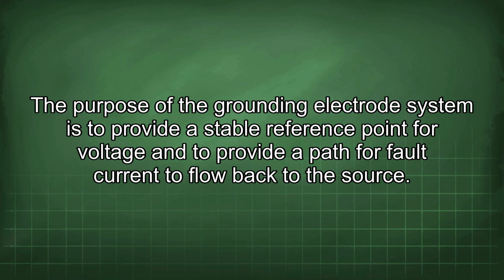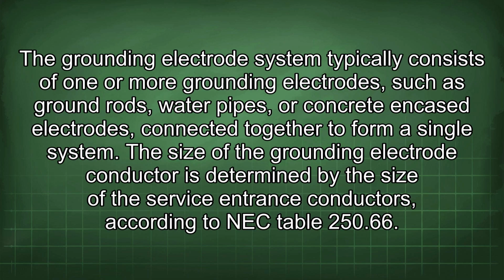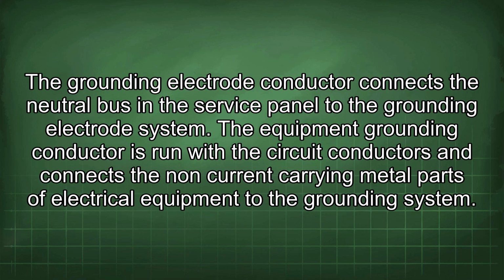The purpose of the grounding electrode system is to provide a stable reference point for voltage and to provide a path for fault current to flow back to the source. The grounding electrode system typically consists of one or more grounding electrodes, such as ground rods, water pipes, or concrete encased electrodes connected together to form a single system. The size of the grounding electrode conductor is determined by the size of the service entrance conductors according to NEC Table 250.66. The grounding electrode conductor connects the neutral bus in the service panel to the grounding electrode system.